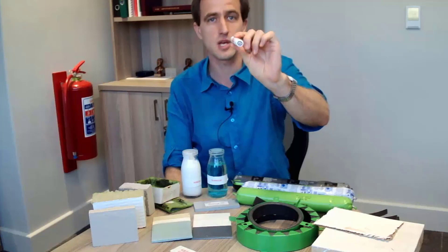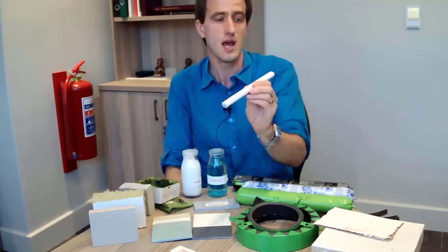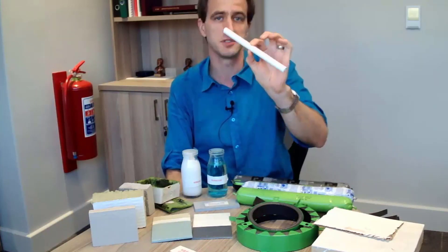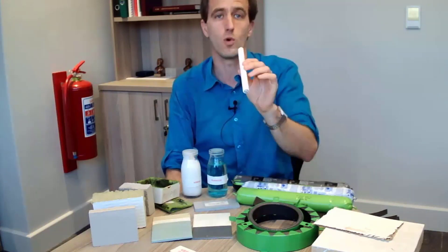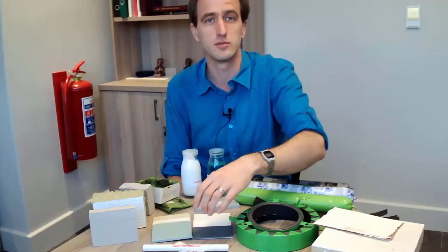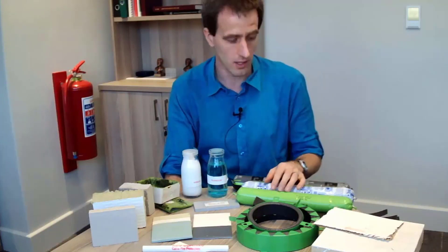You can even get ablative coatings for cables. The main aim of this is to prevent fire from spreading down the cable and taking the fire 50 meters down your factory. This would prevent fire spread, but it won't protect the cable itself from a longer-term fire. If this is an emergency cable, you're in serious trouble. Look carefully at what carries information needed in an emergency — fire alarms, lifts, communication systems — and make sure a different, more protective product is applied to those.